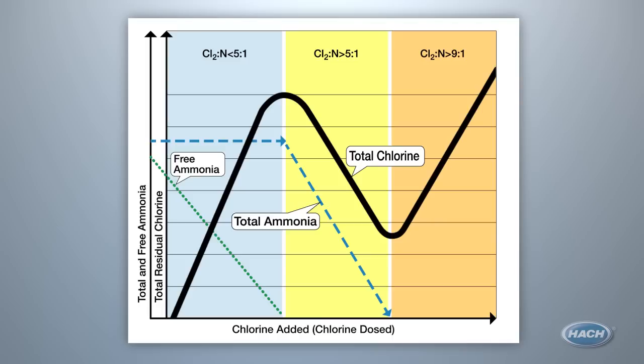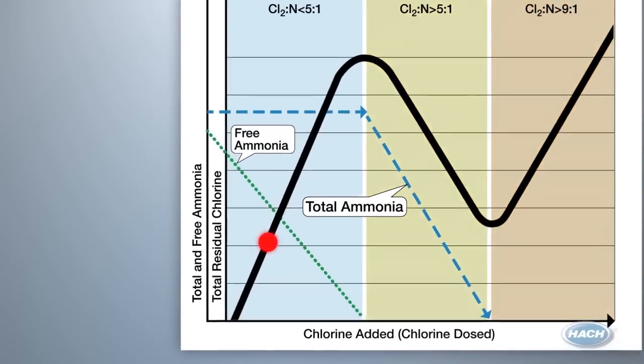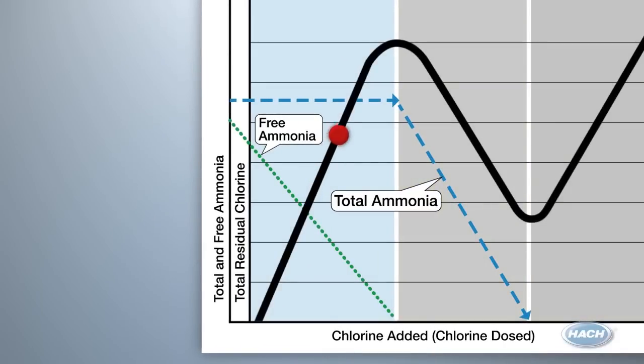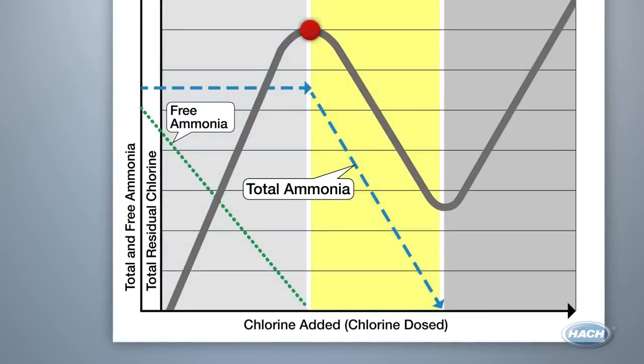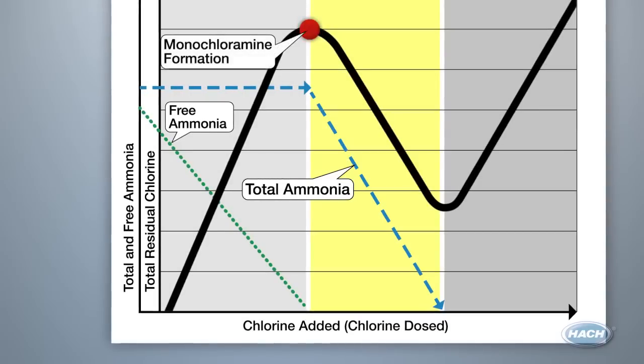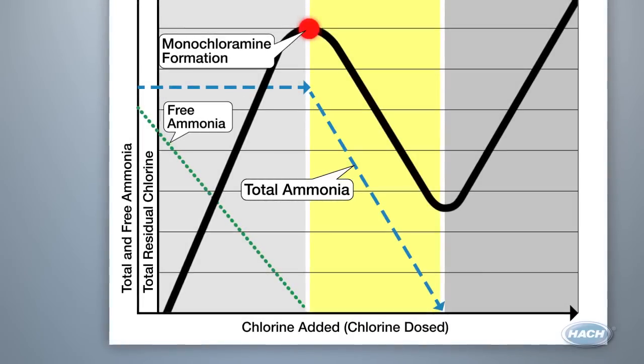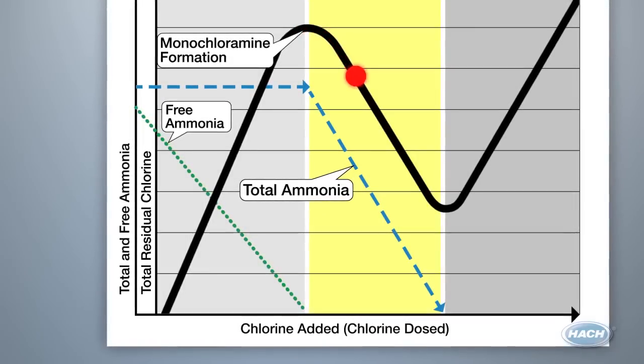So how do you know where your utility's water lies on this chart? Some simple measurements can tell you. For instance, in zone one, you will see total chlorine and a presence of free ammonia. In zone two, you will see total chlorine, monochloramine, total ammonia, but no free ammonia.